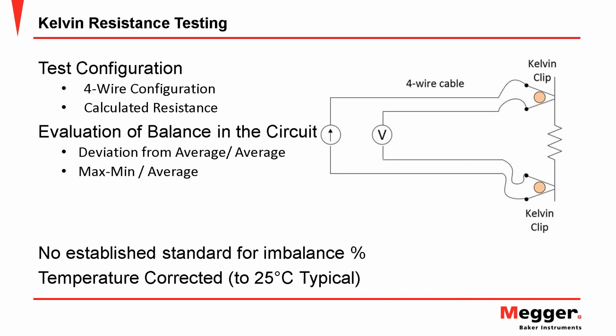So let's start off talking about Kelvin resistance testing. Low voltage resistance testing, when performed specifically on motors, is looking directly for imbalance conditions. Oftentimes we don't know exactly what the resistance should be of a motor because it's not something that we find on the nameplate, but we know that for a 3-phase motor, for the most part, it should be balanced, especially for the larger the motor, the more balance that we should see. There's some inherent imbalance in lower horsepower motors that are randomly wound, for example, in some cases.